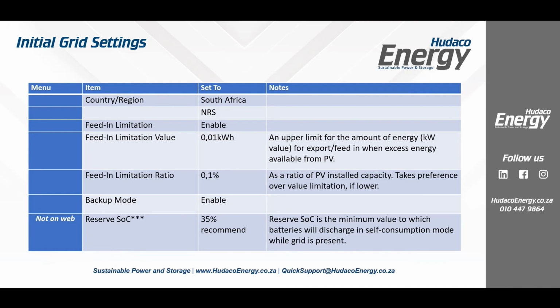So when you first commission the inverter, it's going to come up and it's going to say initial grid. We go down and we select South Africa. Then I think on firmware version 26 and up, it gives us NRS as an option. There are some cases where if you're running version 25, it's completely stable, it's absolutely fine, but it just doesn't ask for NRS at all. It just assumes it. If it does ask for NRS, then you just select NRS as opposed to RRP. RRP doesn't have a lot of settings preset. NRS has all of our local settings already preset.